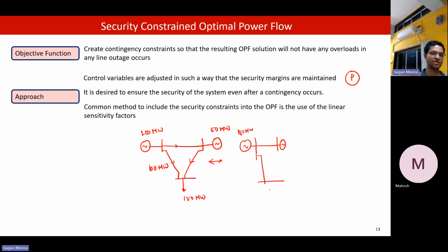In this case, it might not be possible to supply the demand without violating the security margins, and the load needs to be curtailed here. The 50 megawatt of load will be curtailed because it is a very simple, small network with no redundancy as such. If the network could have been like this, and one of these lines goes out, then we can still supply the load. The entire 150 megawatt load can be supplied.